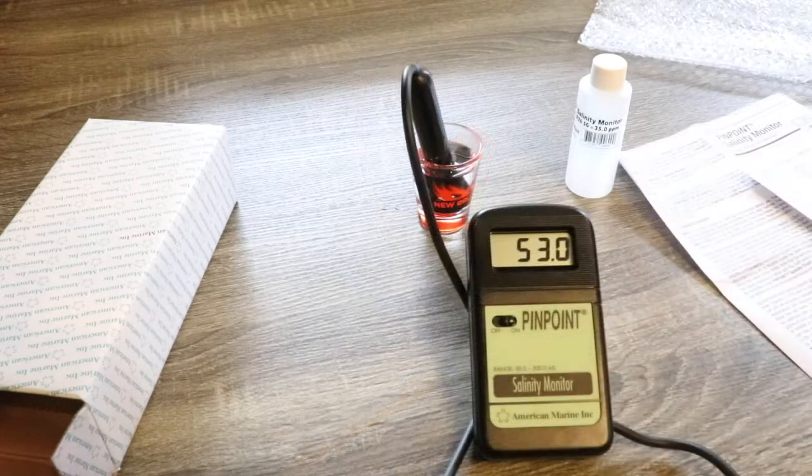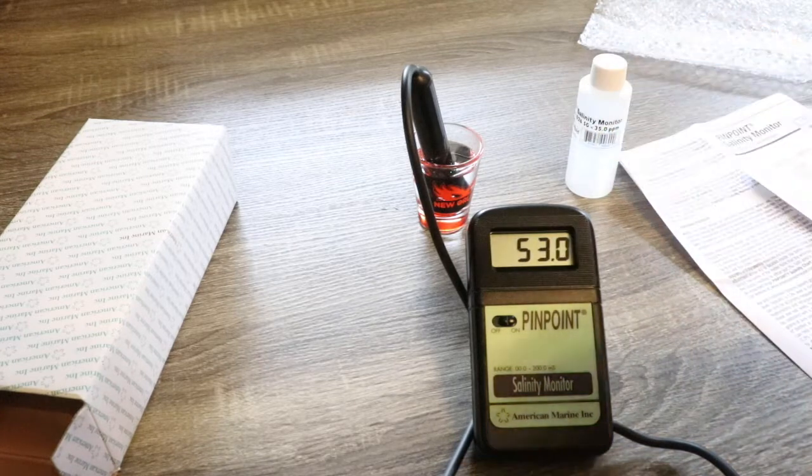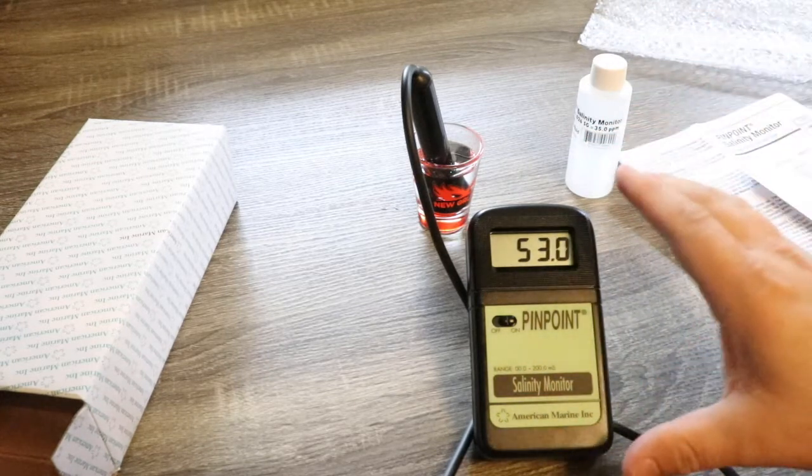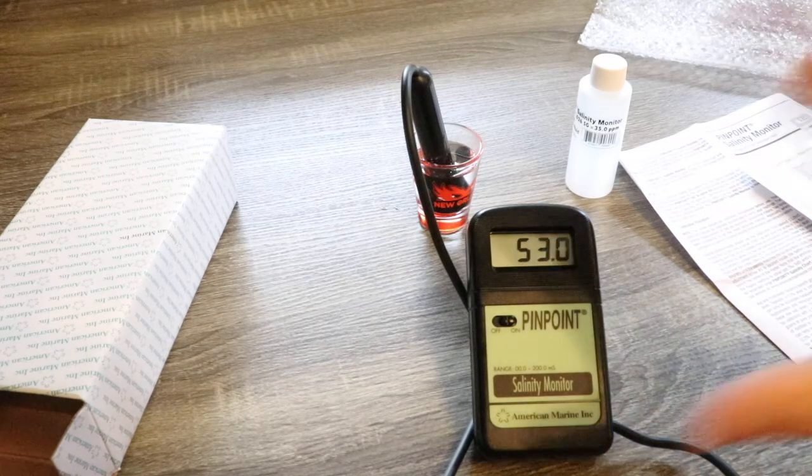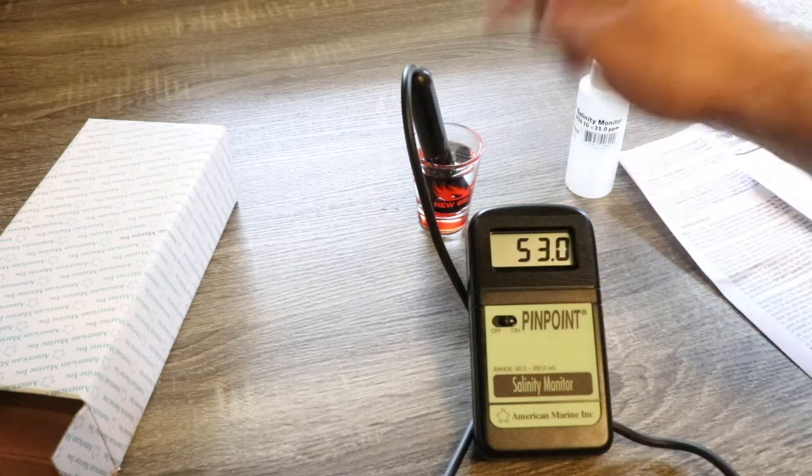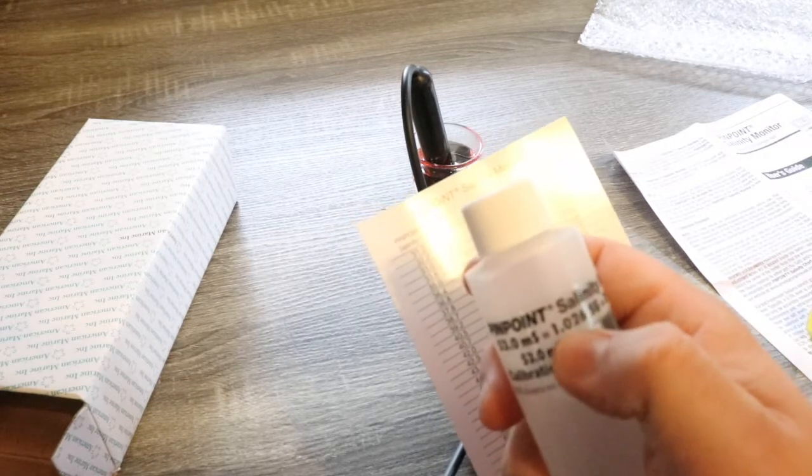All right, so we have the Pinpoint Salinity Monitor calibrated. It's been in the solution for a good five to ten minutes and we are holding at 53.0. Now what this is measuring is conductivity of the solution, and we need to convert that on our chart to get our salinity reading. So the calibration fluid is designed to be at 53.0, and that equals 1.026 specific gravity and 35 parts per thousand salinity.